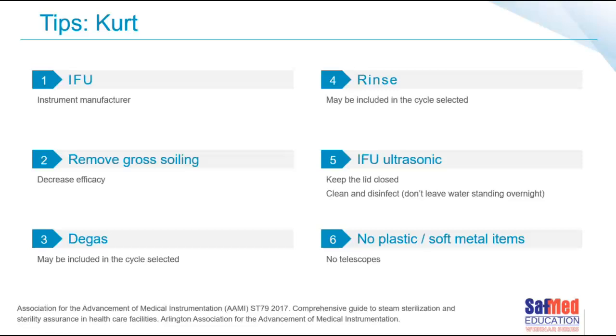Sure. Going through the tips on the screen, we have the instrument manufacturer's instructions for use. That's number one, and it is very, very important. A lot of times we ourselves will put in instruments that are not validated, or whose instructions state that they can't go in an ultrasonic cleaner, and you could of course damage the instrument. Then there are instruments where the detergent or the certain hertz of the ultrasonic cleaner is not correct. The frequency is measured in hertz, and if the hertz is not correct, you can end up damaging your instruments as well. So the instructions for use are very, very important, and you need to follow those protocols.